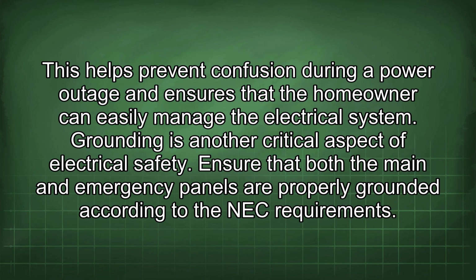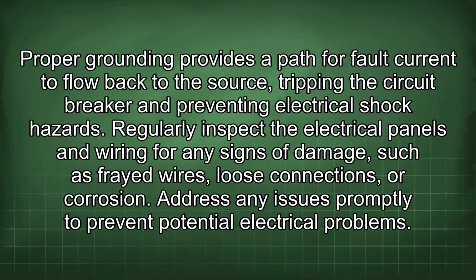Grounding is another critical aspect of electrical safety. Ensure that both the main and emergency panels are properly grounded according to the NEC requirements. Proper grounding provides a path for fault current to flow back to the source, tripping the circuit breaker and preventing electrical shock hazards. Regularly inspect the electrical panels and wiring for any signs of damage, such as frayed wires, loose connections, or corrosion. Address any issues promptly to prevent potential electrical problems.